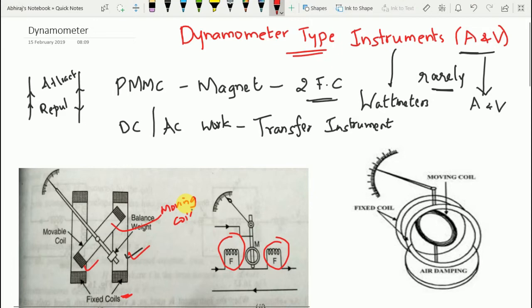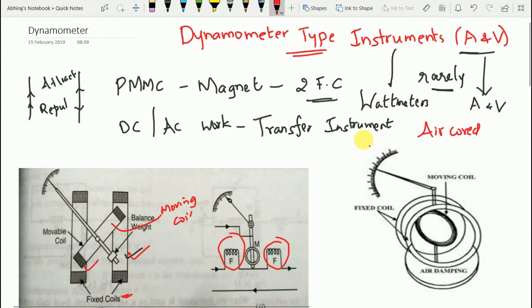The coils used here are air-core coils. We use air-core coils in order to avoid hysteresis, eddy currents, and other errors when this type of instrument is used on AC. So the fixed coil is divided into two halves — split into two parts F and F.